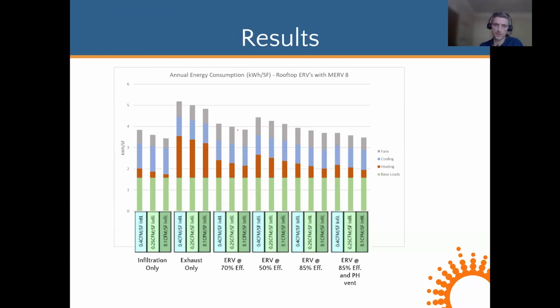And here's the energy consumption there. We can see there's a little bit of an increase in total consumption. But again, still lower for all of the ERV scenarios in the exhaust only scenario because of all that heat recovery. And again, once we get down to passive house level ventilation rates and high energy recovery, we're offsetting that additional ventilation load almost entirely.